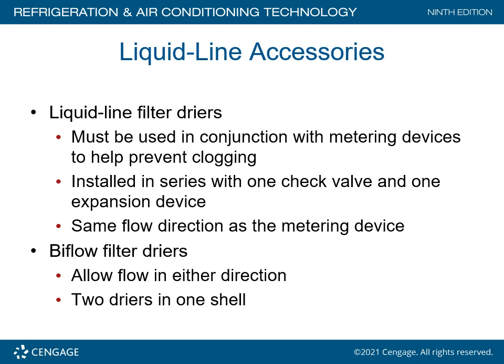Liquid line accessories. One thing that's really important is liquid line filter dryers. The reason I say that is liquid line filter dryers for heat pumps are different than on a standard split system air conditioning design, because the filter dryer is designed to allow refrigerant to flow in either direction. So when you put a liquid line filter dryer on a modern 410A split system heat pump, that filter dryer has to be a bi-flow design.